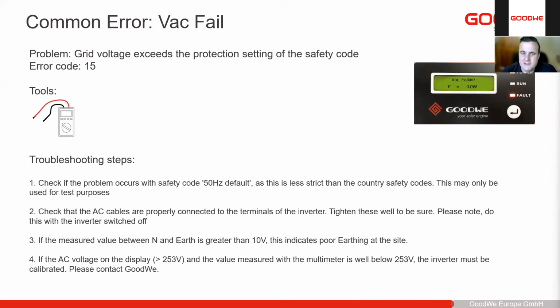So then we have VAC failure. The grid voltage exceeds the protection safety of the safety code. So VAC failure is either our voltage is too low or too high for the safety code which we've set on the device. Normally you can change the country code on the device to 50 Hz default and see if that thing disappears. Just for testing purposes to see whether it is a problem with the voltage.